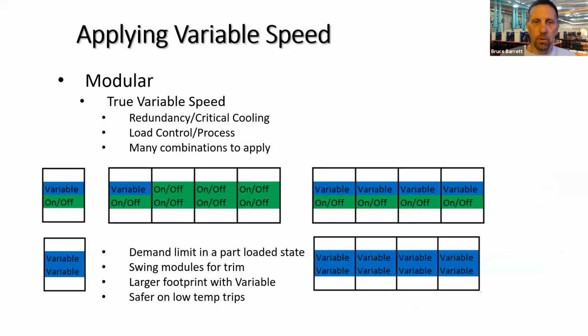What does that mean for a water-cooled job? Well, we could do single modules. We can do an array of chillers with one of those compressors being variable. It's going to be your first on, last off. We can add more compressors as variable. It's going to increase your ability to do tighter temperature control. Of course, we could do all of the compressors with variable speed. So we're trying to be cost conscious as well as efficiency and electrical conscious in applying that variable speed compressor. You do not have to go all in, all or nothing.